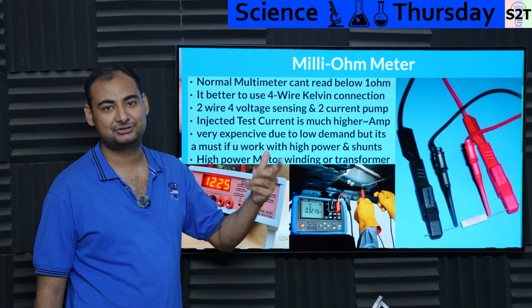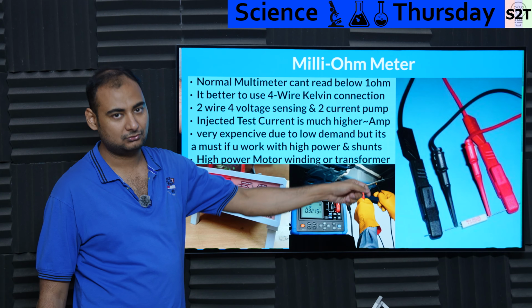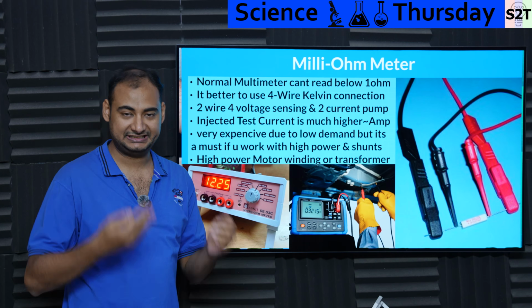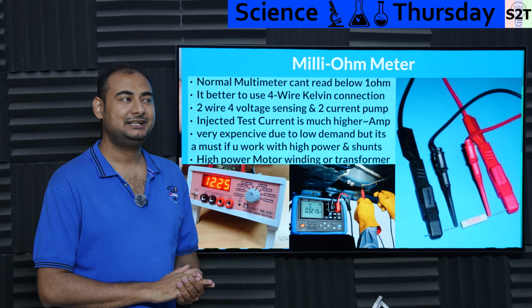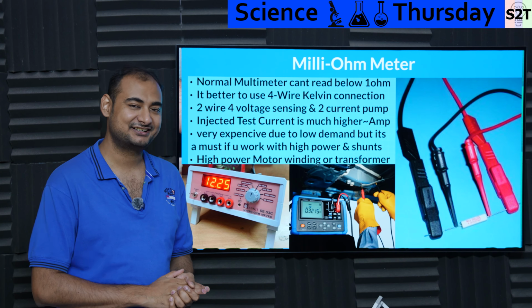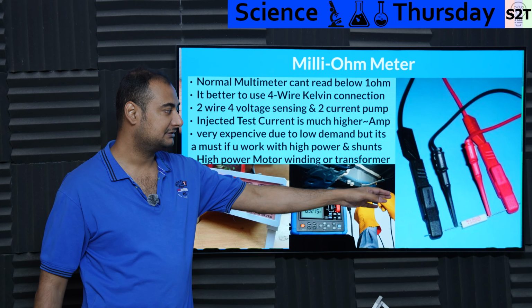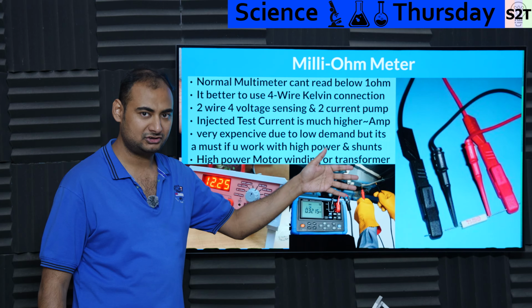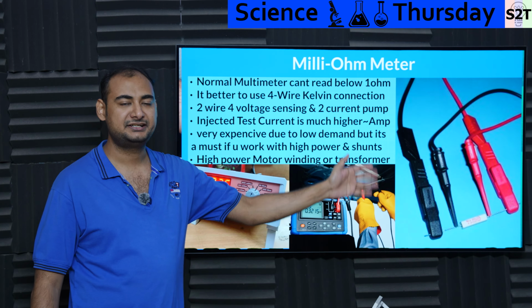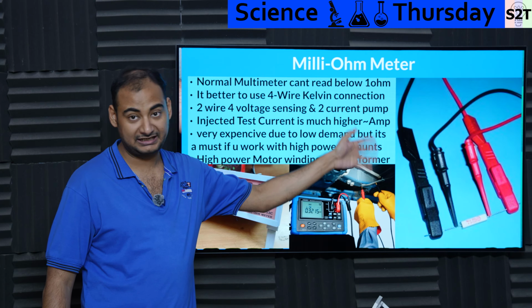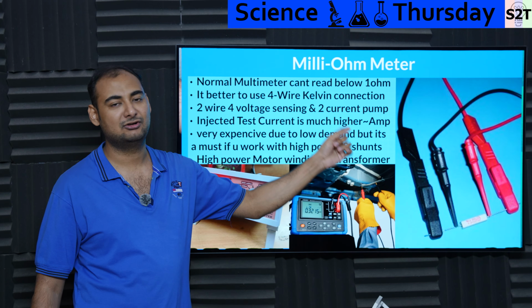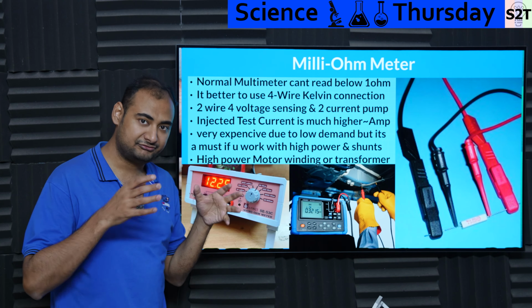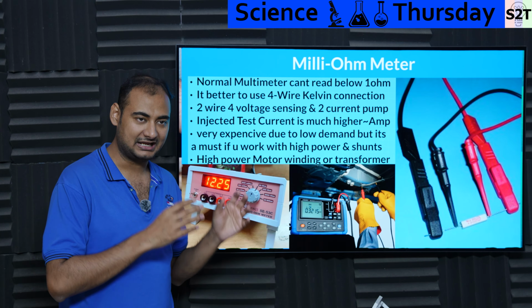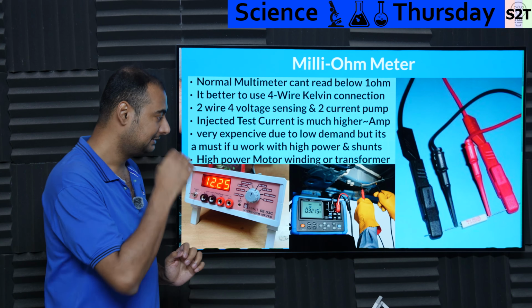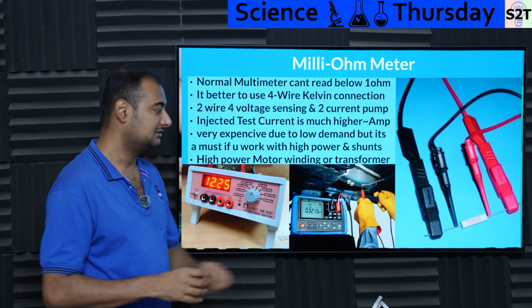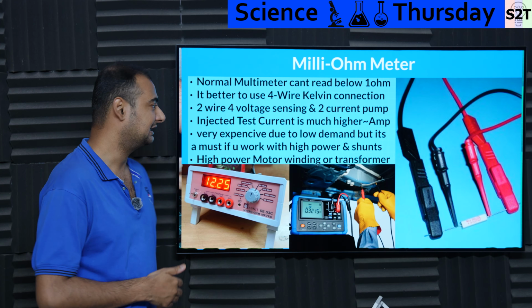Because physics has this cheat code, meaning if you're sending current through a wire that is not made out of superconductor, it will have voltage drop. However, if you're measuring with something else, that will not have the current draw. So because of the high impedance of a voltmeter, you can send the majority, like 99.999% of the energy, through a different cable, and the voltage drop will not affect your voltmeter reading. So that is a fundamental necessity to have a better signal to noise ratio. That's why whenever you go into precision instruments, they are always 4 wire measurement. It has to be. You cannot trick around.